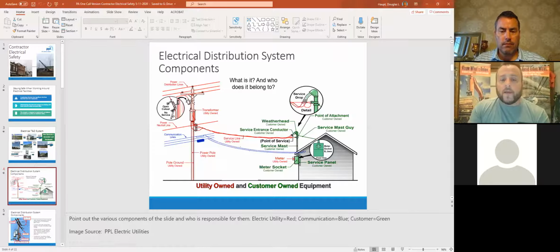Out on the pole: top wires, transformer. The wire just below the transformer is our neutral or ground wire. So our operating space on the pole runs from the ground wire up to the top of the pole—that's where our facilities reside. Once you get below that system neutral, everything below becomes communication lines—fiber, phone, and so on—brought into the homes as well. So that's what's out on the pole, what's ours, and what's the responsibility of a homeowner or business.